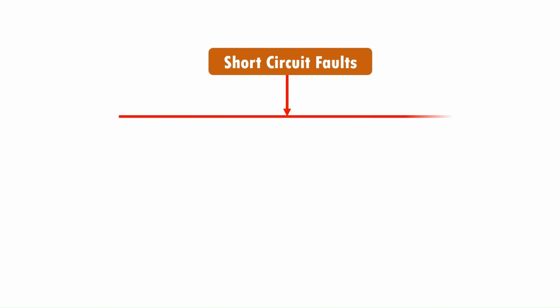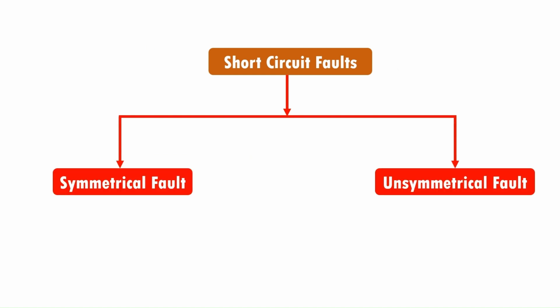Next important type of the fault is short circuit fault. In this type of fault, the conductors of the different phases come in contact with each other or with a power line, power transformer or any other circuit element, due to which a large current flows in one or two phases of the system. The short circuit fault is divided into symmetrical and unsymmetrical fault.